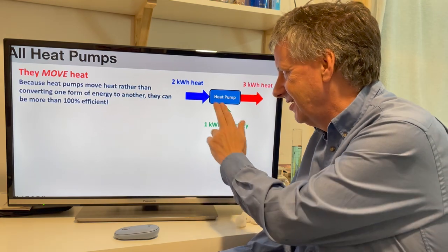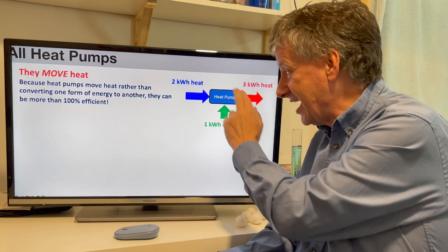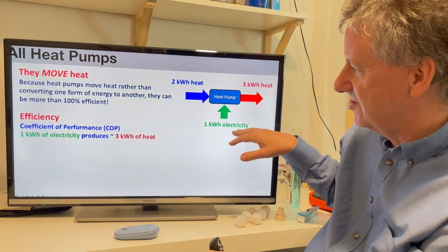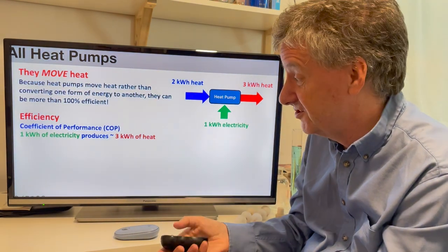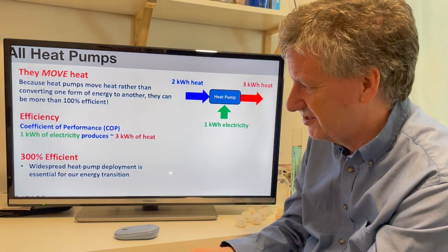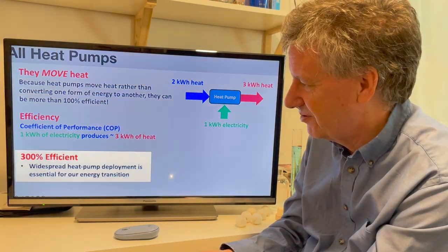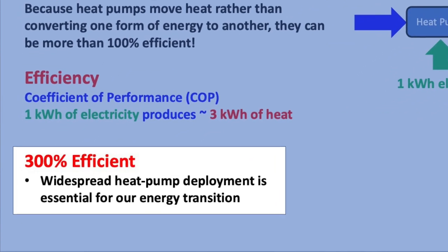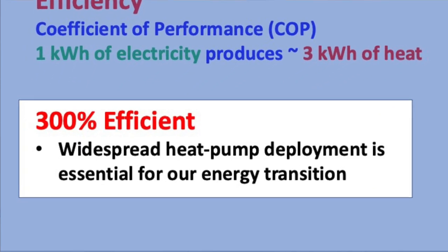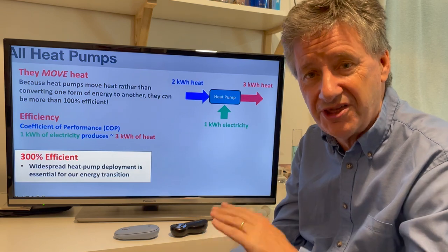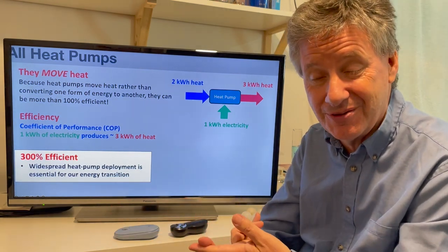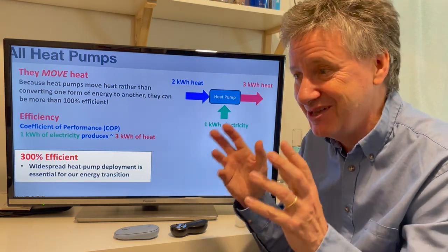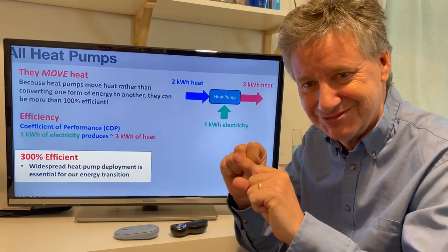The thing all heat pumps share is that they move heat. When we use one kilowatt of renewable electricity — precious stuff, we don't have enough of it — we can move two kilowatts of heat and get three kilowatts out as heat altogether. This ratio of heat output to electricity input is called the coefficient of performance, or efficiency. Typically heat pumps are 300% efficient, and they're getting more efficient every year. Why does it matter? Because if we use a heat pump rather than an electrical heater to heat our homes with renewable electricity, we only need one-third the amount of renewable electricity — one-third the wind farms, one-third the solar, one-third the nuclear. That makes a massive difference.